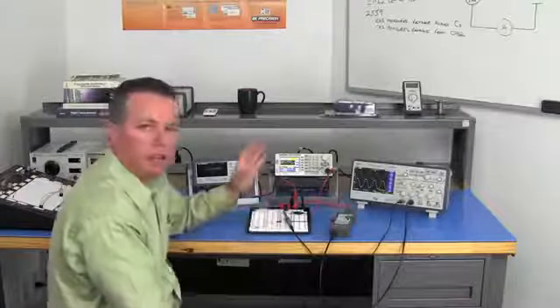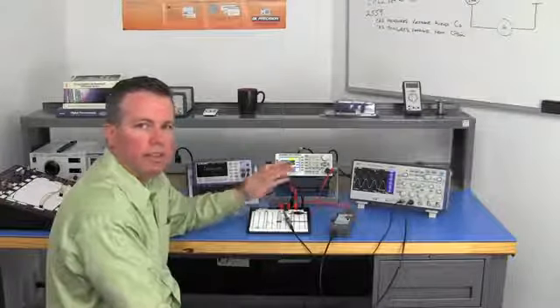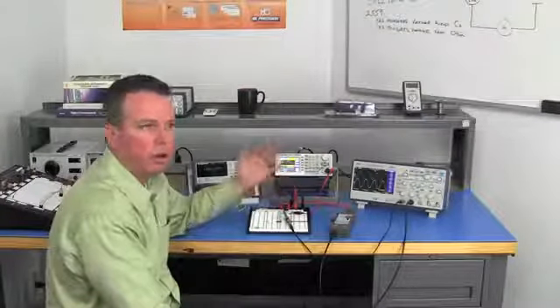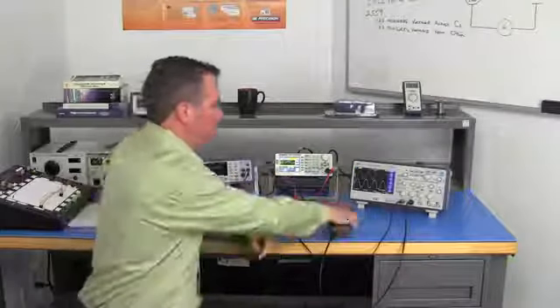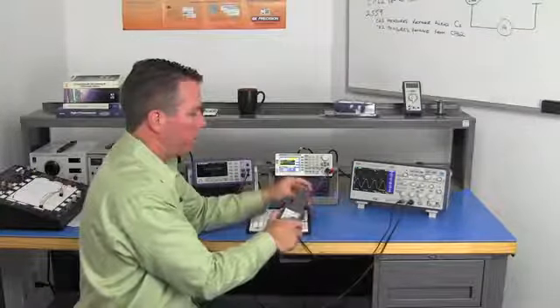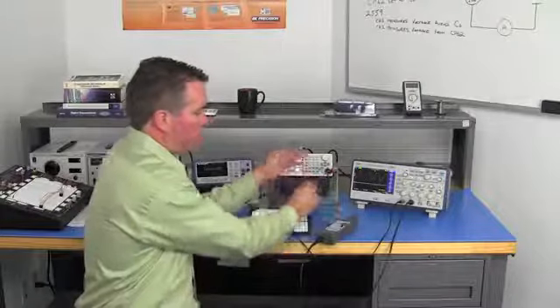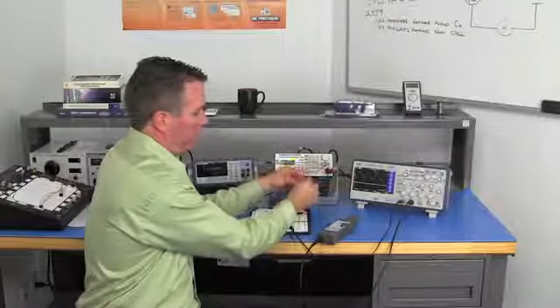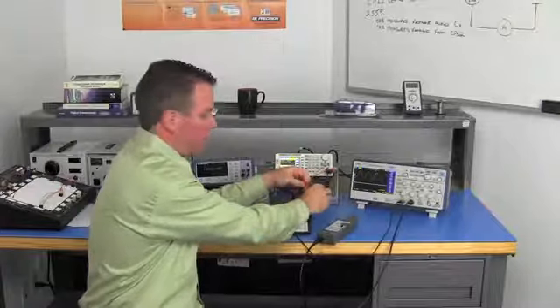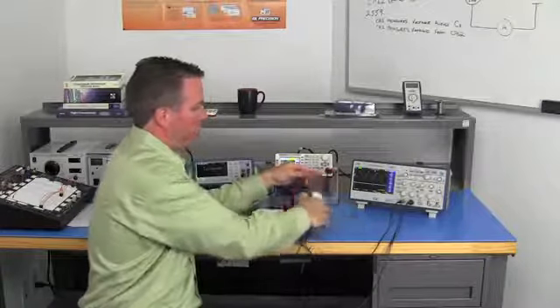So if I was measuring a current value even less than what we're measuring here, like around 60 milliamps or whatever it might be, one little trick you can do with current probes is make loops, and that will multiply the value you're measuring.